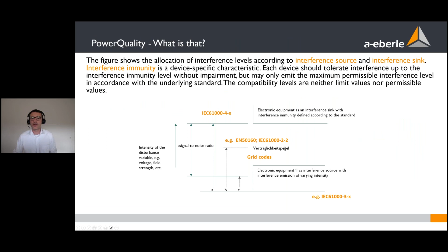So the standardization in the field of grid codes, for example. What are the grid codes? What are the production requirements? What helps us there is the standardization in Europe. We have, for example, EN 50160 for high voltage systems, medium voltage systems, and also low voltage systems. This helps us to provide general stability inside the grid. In industry, a worldwide standard is available, and this is the IEC standardization, IEC 61000-2-4, to prevent these interactions. And there are 3 classes available: class 1, class 2, class 3.